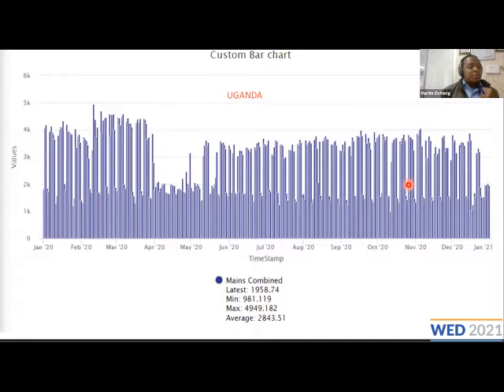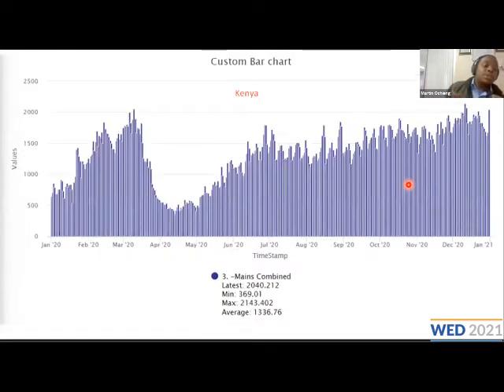One thing we can draw from this is that we can now understand the true base load for this particular facility and put it around 2,000 kilowatt hours. These are scenarios where most commercial buildings and hotels went completely down, and it indicates that there's a significant base load even when the facility is not being used. So maybe there's an opportunity there to look at that consumption and identify what you can reduce when you're not using the whole building. You can do the same for the Kenyan case, which in this case is a hotel.